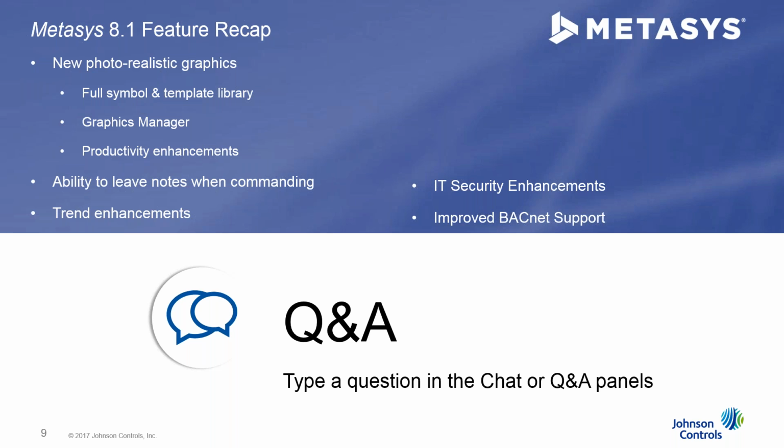Okay, thanks. And are multiple graphics aliased, or is every graphic created individually? Graphics can be aliased. So behind the scenes, when we configure the Metasys UI, all, for instance, VAV boxes or all fan coils, they get an equipment definition. And we take that graphic and apply it to the equipment definition, and all of a sudden all those VAV boxes in the Metasys UI get that same graphic. Along with that, we'll hide and show symbol elements. Let's say there's a VAV that was cooling only, we're going to automatically hide that cooling coil on the unit that's cooling only. On the unit with the reheat coil, we'll show that symbol. But there's only one graphic that would drive that. You can also override graphics on an individual basis through what we call exception graphics.